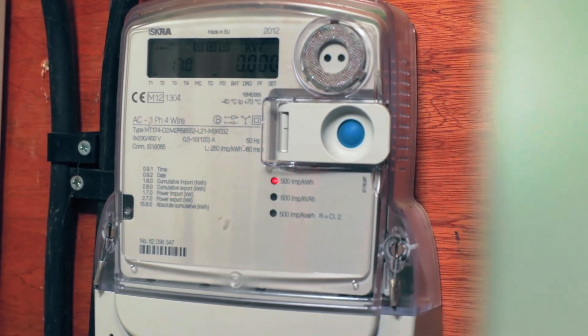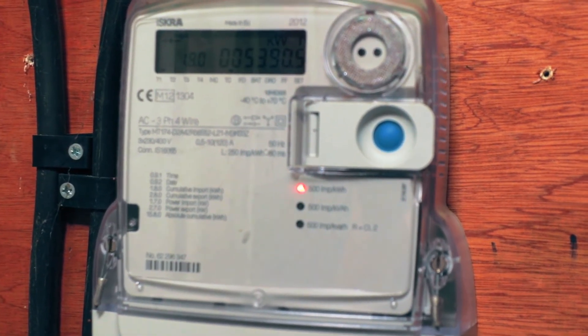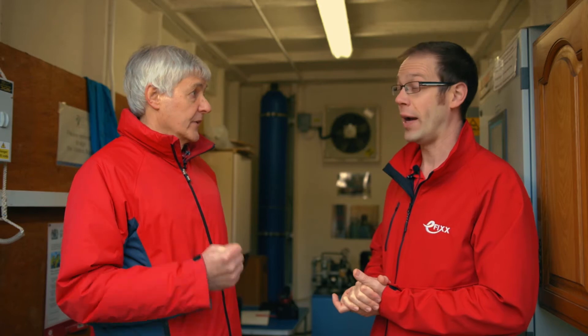We really love this project — it's very worthy — but of course in order for it to be viable it's got to be able to pay back the investment costs. Down the end tucked on the right we've got possibly one of the most critical pieces — the meter. What's that telling us about the electricity we're producing? That's telling us what we're generating. At the moment 40 kilowatts — over a year we'll probably do 108 megawatt hours a year. Which is quite a sizeable amount for the size of river that we're on.